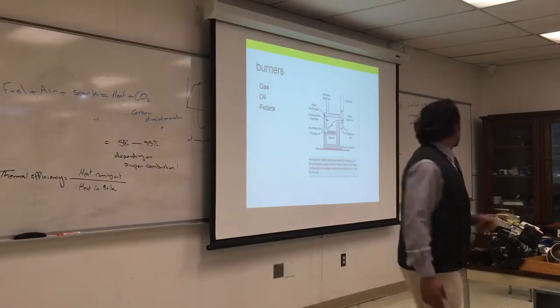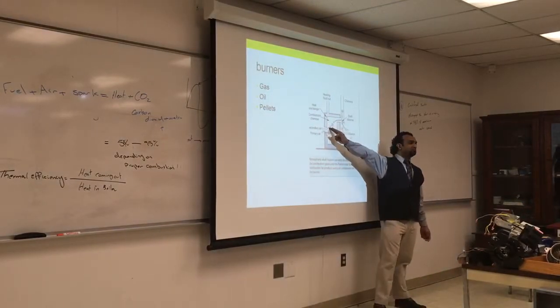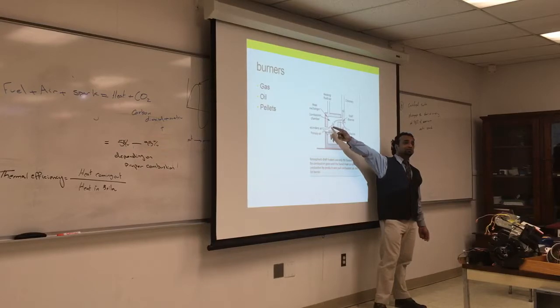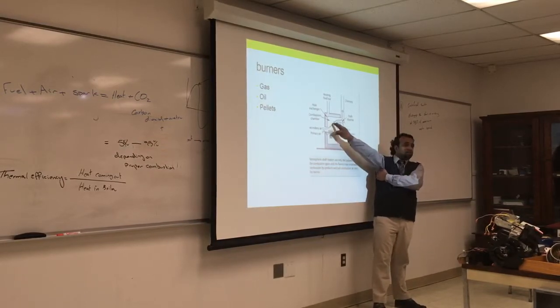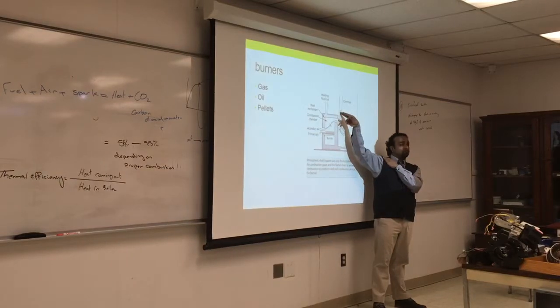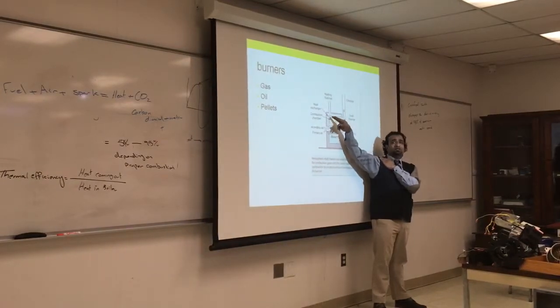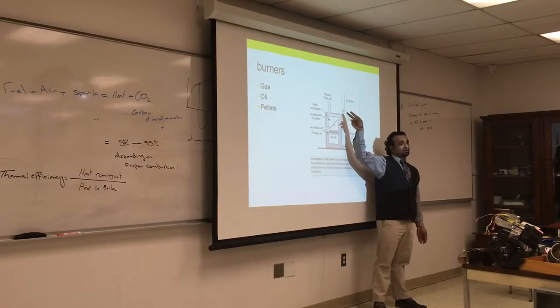So, what is the temperature in the chamber? Let's say we're heating with oil. What is the temperature here? 160, 180? No, more than that. Inside the chamber of a furnace? 600? Oh, I was thinking 600. Yeah, sorry, 650. That's great. 650 is the combustion temperature of oil. What is the temperature here? 450. So I'm sucking in only 200. So I'm dumping 450 degrees into the atmosphere. That doesn't seem smart. But you cannot have it lower.